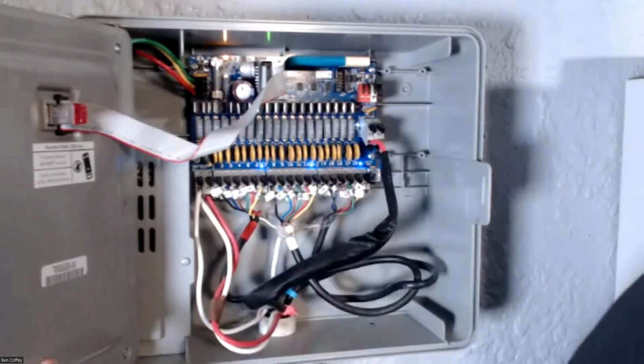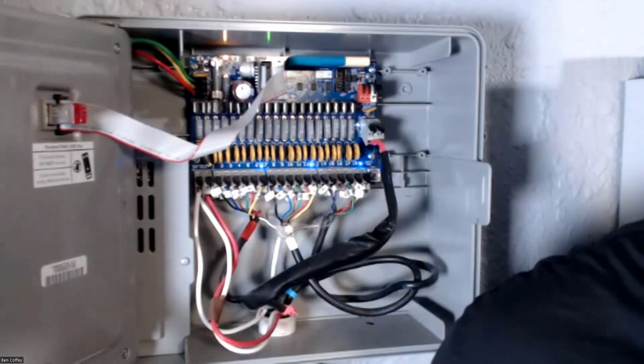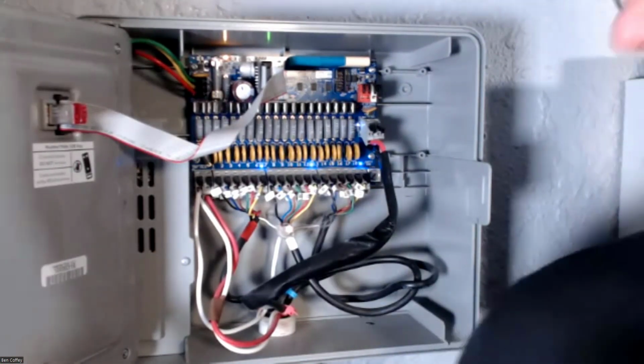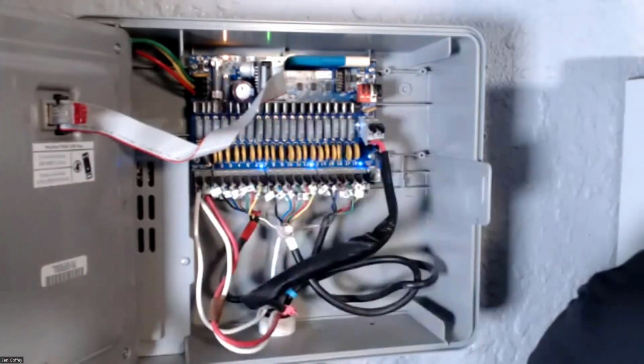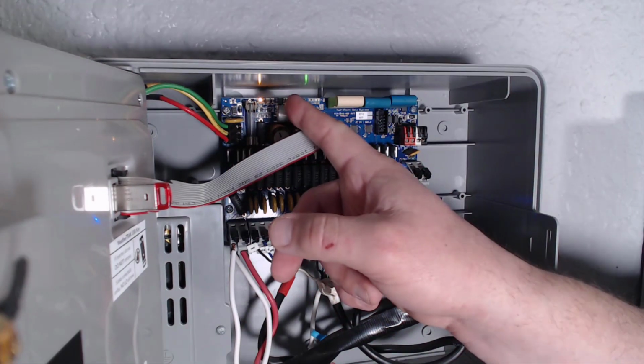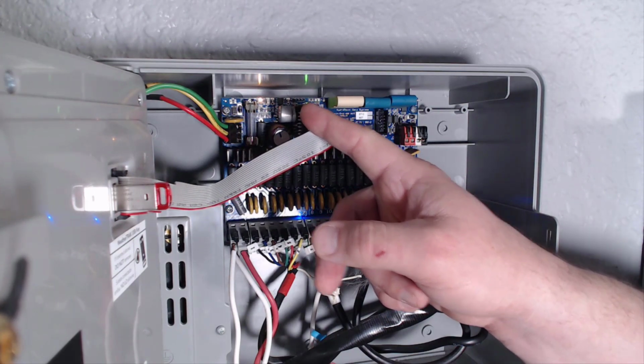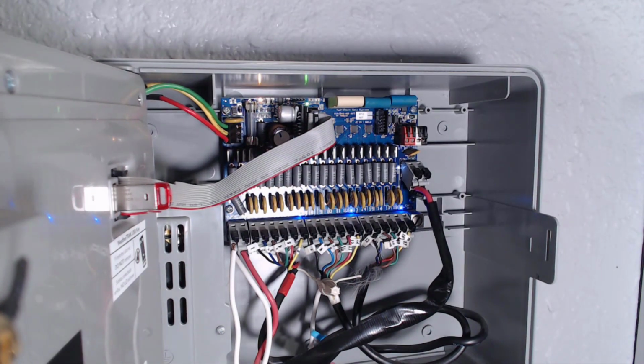We plug in the panel through this ribbon cable right there, and this is where we get to our first and second LED diagnostics. Can you tell me what you see in that yellow light and that green light? Back to the conversation about power and fuses - this is a good time to bring this up. We no longer need a voltmeter for these LED diagnostic lights. What this allows us to accomplish is that orange light, if you could point that out, right there on the top - that actually indicates that we have 24 volts coming into the system, onto the terminal board in this case. That's what that light indicates.